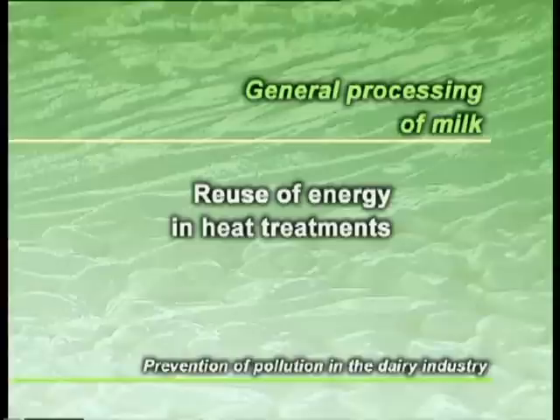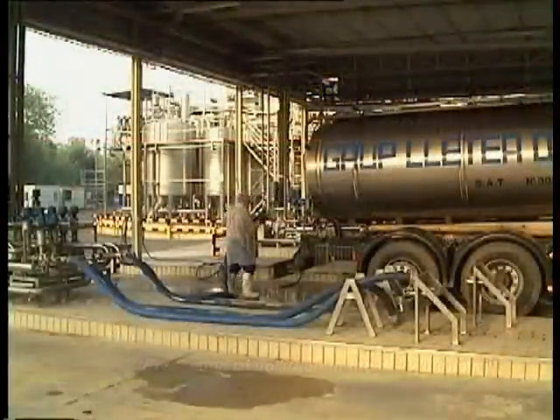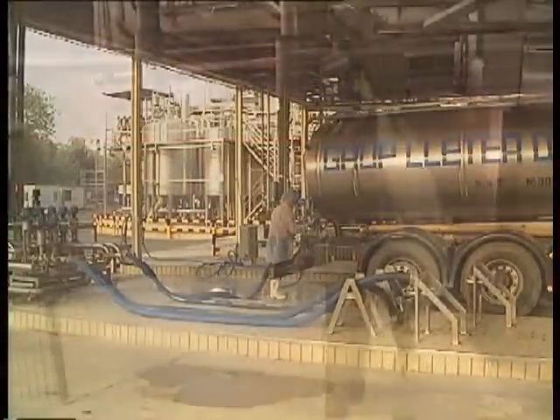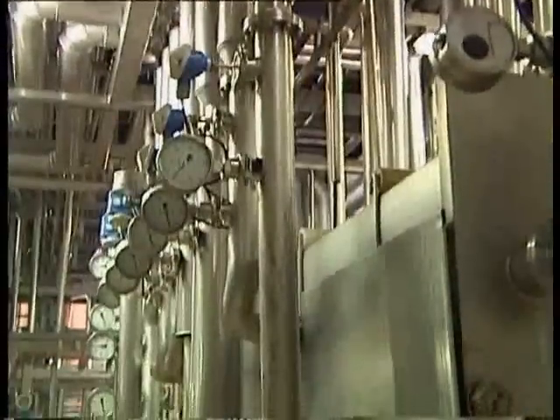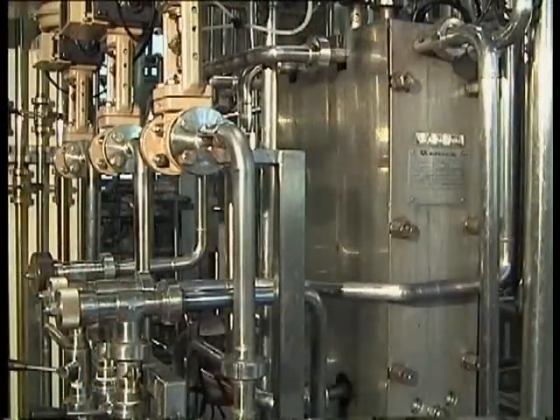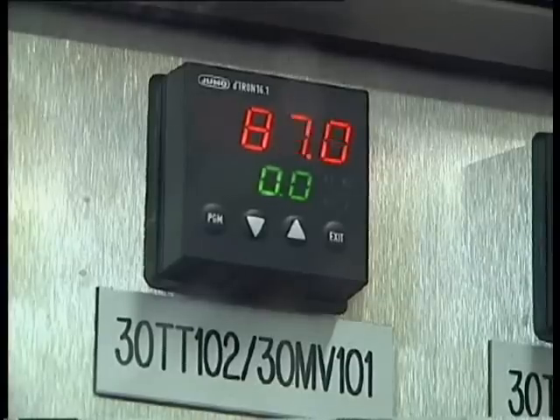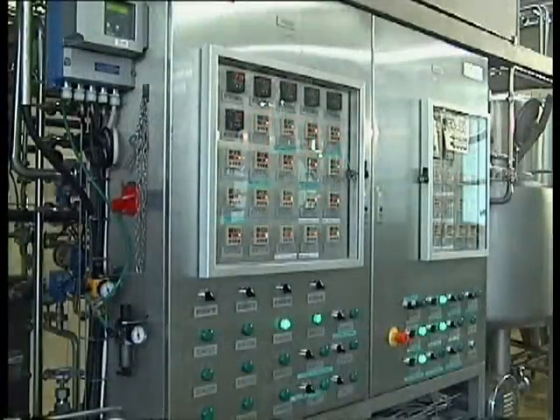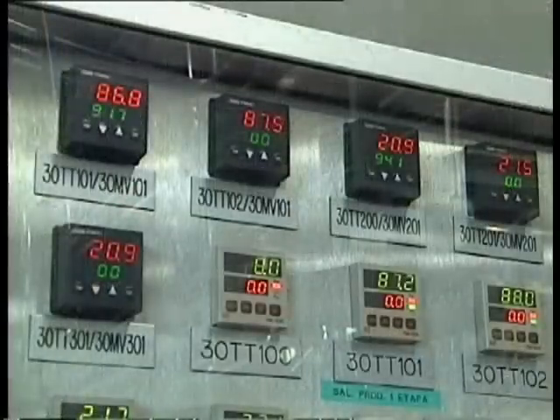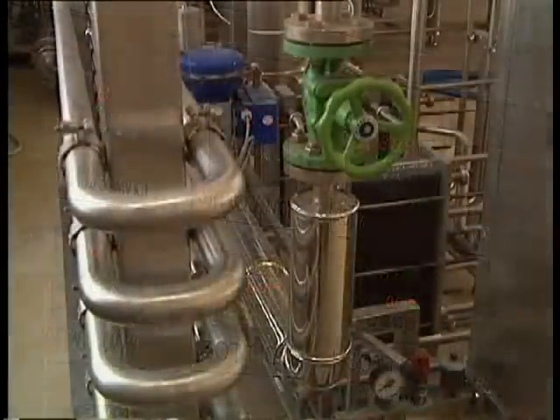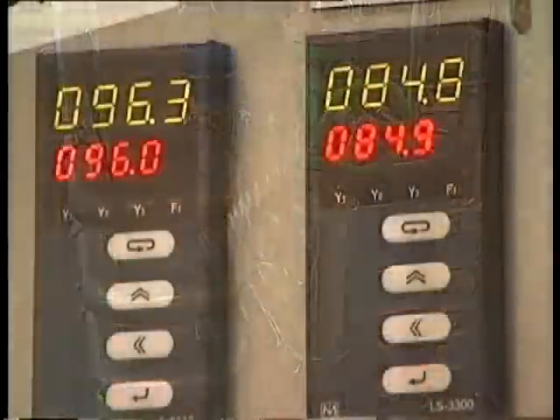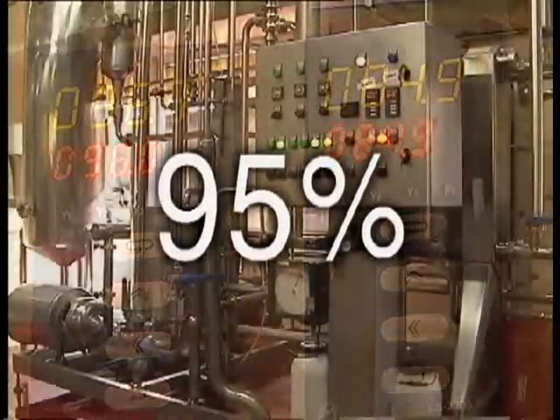Reuse of energy in heat treatments. The total or partial elimination of milk microorganisms can be obtained from pasteurization, sterilization or UHT treatment. These treatments maintain the milk at different temperatures for specific periods of time. The use of heat treatment equipment with recovery sections that use energy from the heated product to heat the cold product allows us to save up to 95% of the energy used during the process.